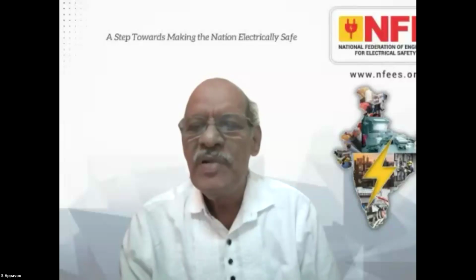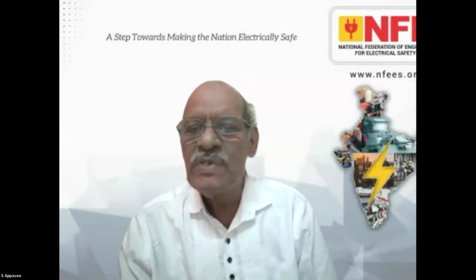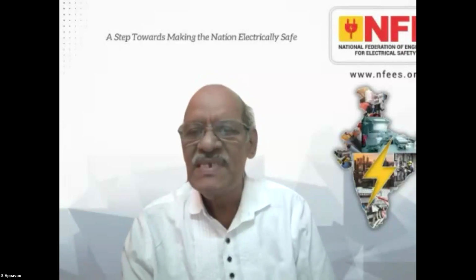Then another question is from Pattabiram Suresh. For an independent house, is a lightning arrestor provision a must? Okay, this actually depends on your risk assessment. If you have done a risk assessment and it shows that it is not needed, then it is not needed. But if it says yes, then it is better to have an LPS system. But if the risk assessment says no, then you don't need to have one. But you are supposed to have an SPD, 100%, in the incoming power line. That is more dangerous than the lightning arrestor, so that is more important.